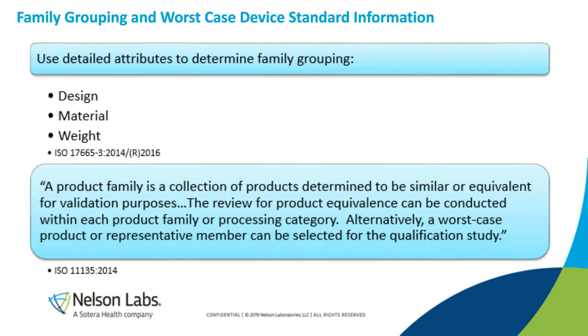ISO 17665-3, published in 2014 and then republished in 2016, details attributes to determine family groupings, which include design, material, and weight. There is also a specific classification of each attribute of the sterilization families that is included in this document. Also, ISO 11135 specifies that a product family is a collection of products determined to be similar or equivalent for a validation process. It also specifies that the review for product equivalence can be conducted within each product family or processing category. Alternatively, a worst-case product or representative member can be selected for the qualification study.